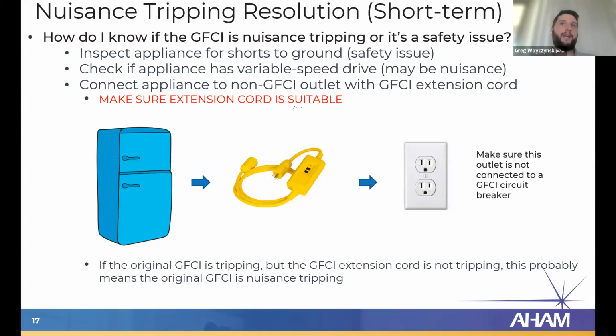You can check if the appliance has a variable speed drive. So for it to be nuisance tripping, it doesn't have to have a variable speed drive, but a variable speed drive, from what we've seen, makes it more likely to be nuisance tripping. So you can check the component list or just check the information online for that model, see if it has a variable speed drive. Another thing, a quick test you can do is you can connect the appliance to a non-GFCI outlet with a GFCI extension cord. And you want to make sure the extension cord is suitable. Proper wire gauge, you're not plugging it in while it's around the reel so the extension cord melts, all that stuff. Make sure you're using the extension cord in a suitable way.